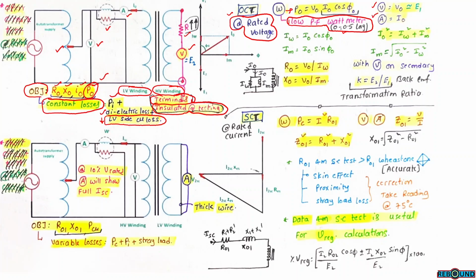The wattmeter gives the no load power losses, P0 equals V0 I0 cos phi naught. The ammeter gives the no load current I0, and the term I0 cos phi naught is considered as IW, the working component. So from these two terms, I0 and IW, the magnetizing component can be calculated. The magnetizing current IM equals under root I0 square minus IW square. The magnetizing current component is I0 sin phi naught.